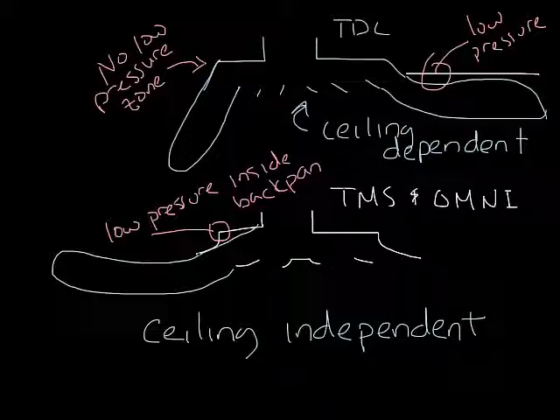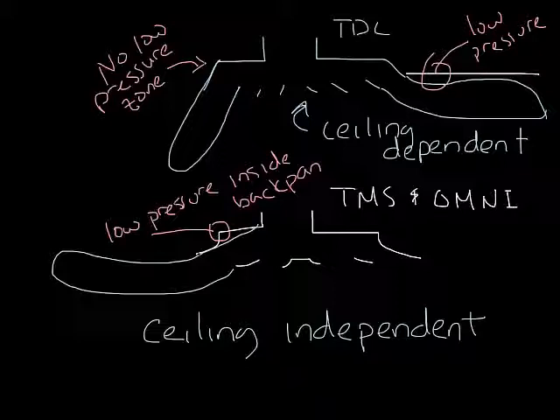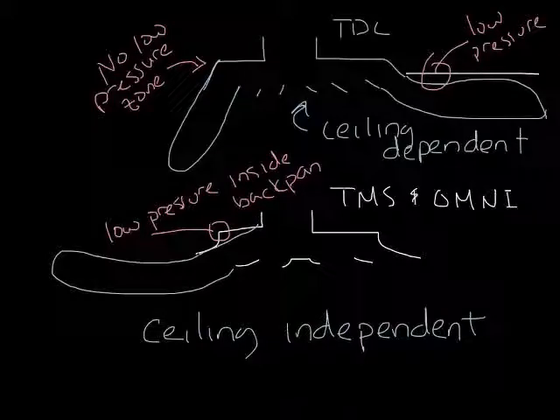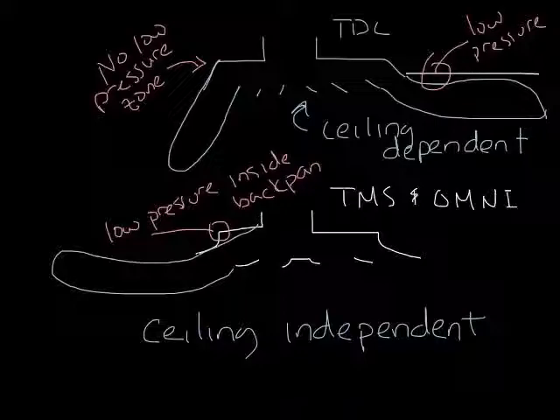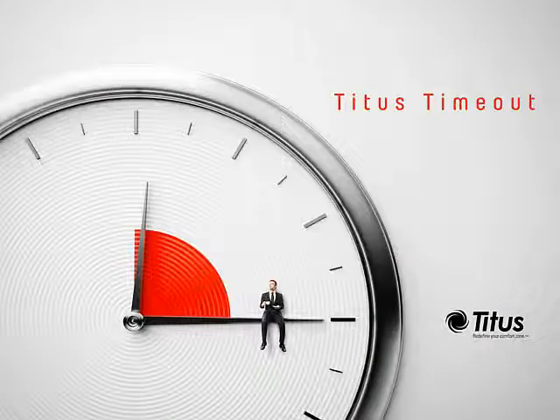So you need to remember that if you have an open ceiling, you need to select a ceiling-independent diffuser to maintain the air pattern and allow the diffuser to perform the way it should for optimal mixing and comfort. So that covers ceiling-dependence and ceiling-independence. Thanks for taking a time out with us.